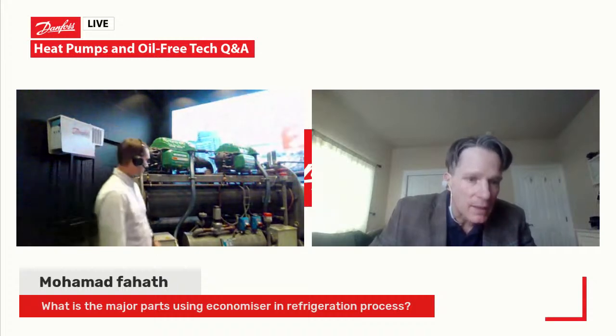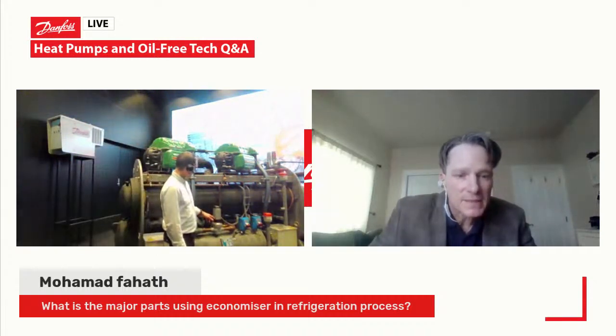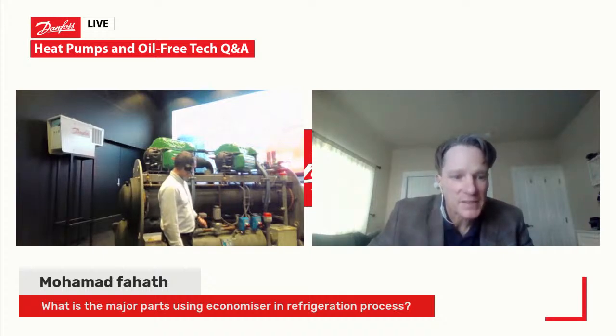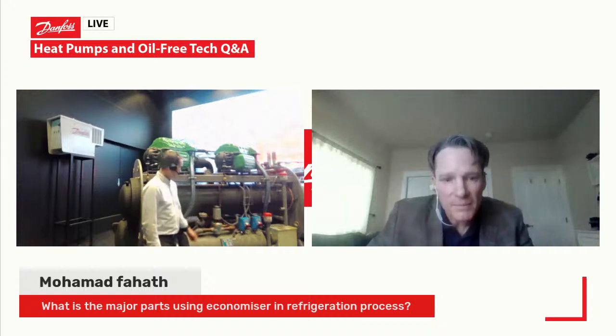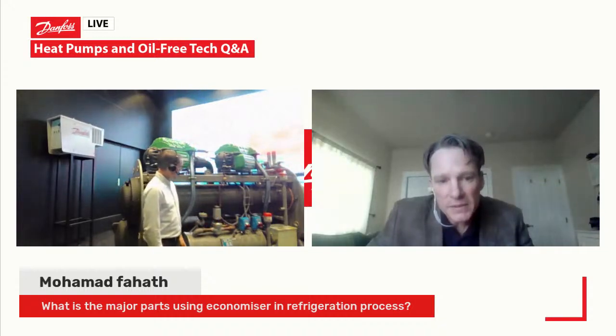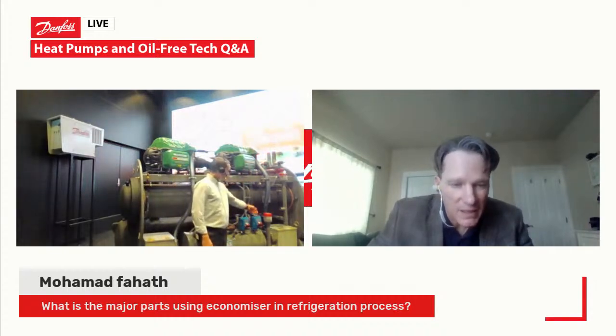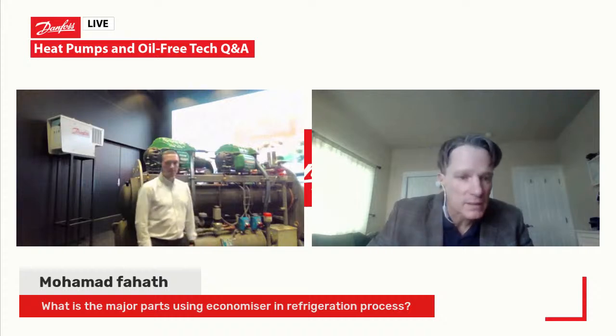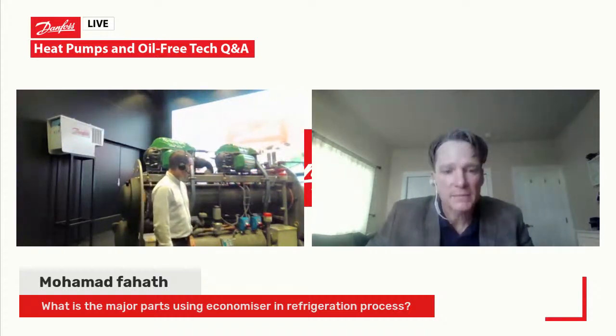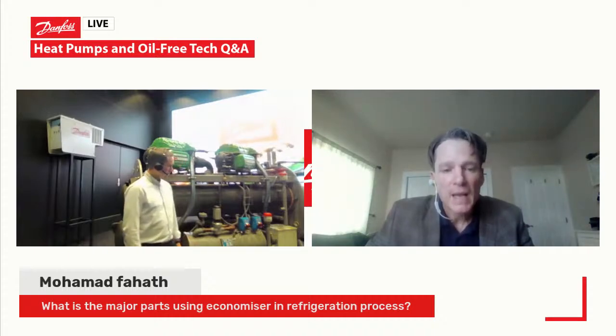But the components you see, you'll see right on top of the flash tank—Jonas, if you want to point to the flash tank—right on top is the Danfoss EXV and actuator for that economizer. To the right you'll see the liquid level sensor, specifically the Danfoss AKS 4100, used as the liquid level sensor on that flash tank economizer system. Those are the primary components, and of course you have the piping associated with it. Generally, the piping from the flash tank economizer goes back to the intermediate stage of the compression process after it's flashed off, and then the pure liquid, which is the purpose of the economizer, is distributed to the evaporator.